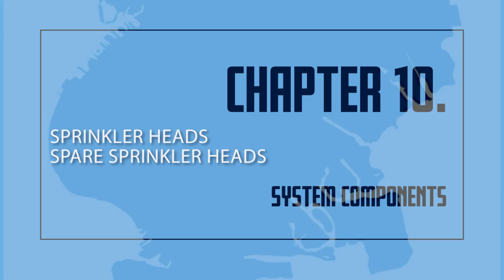Under 300 sprinklers, 6 spares are required. For 301 to 1,000 sprinklers, 12 spares are required. If there are over 1,000 sprinklers, 24 spares are required.